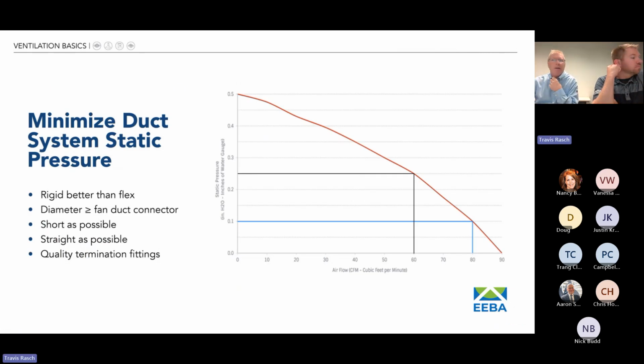So static pressure is very important. If you have a background in HVAC, you're probably familiar with duct static pressure, but for those who aren't, it's an extremely important concept. Static pressure is a measure of resistance to airflow. As your bath fan or ERV is trying to push exhaust gases out of your home, or pull them in in the case of an ERV, you want that duct run to be as short and straight as possible, low static pressure, so that ventilation device can do its job efficiently.